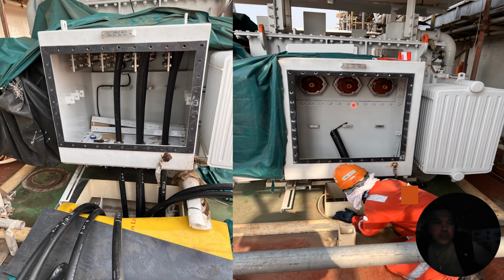And as a construction team, you need to see your single line diagram. You need to check your cable schedule, and before you lay your cable, all cables must be properly measured and checked accordingly, so that the length is appropriate up to the end-to-end connections. So we will not have any cables cut that cannot reach the other equipment. This should be verified through the cable schedule, because as per the designer, they have a 20% extended cable length in their cable calculation.